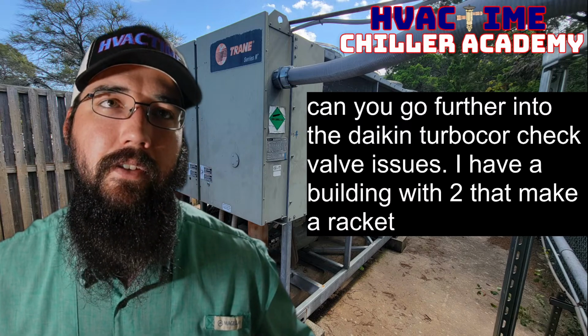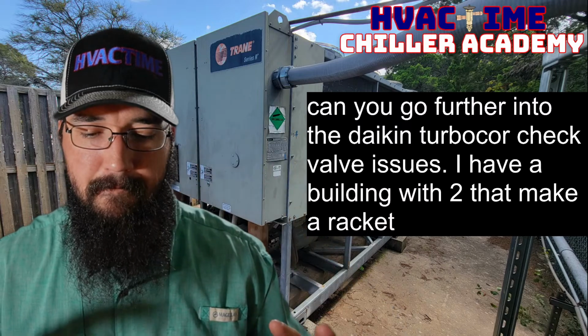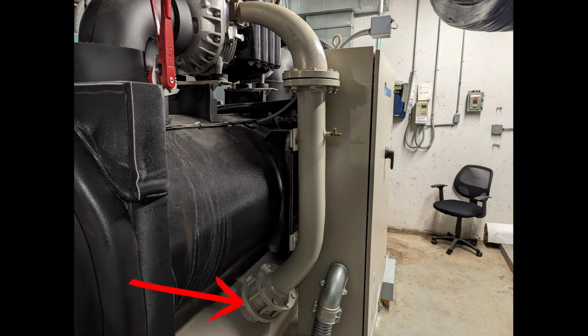So one of the things that Turbocors do, and they're not the only ones, is there's a check valve in the discharge line. We can come over here and look at this. So the check valve is right down here, and Daikin has gone through a number of iterations on this. Here's your Turbocor discharge coming over, and they've put them in a few different locations. The tonnage of your machine plays a part in this. But the very early versions of the machines had a particular style that had really bad trouble with breaking. In some cases it had a swing style at one point. They also had one that's basically split in half, with a core shaft that opens up on either side. And the one they're using now is basically the whole center pushes back on a spring, opens up the check, once it builds up enough force.